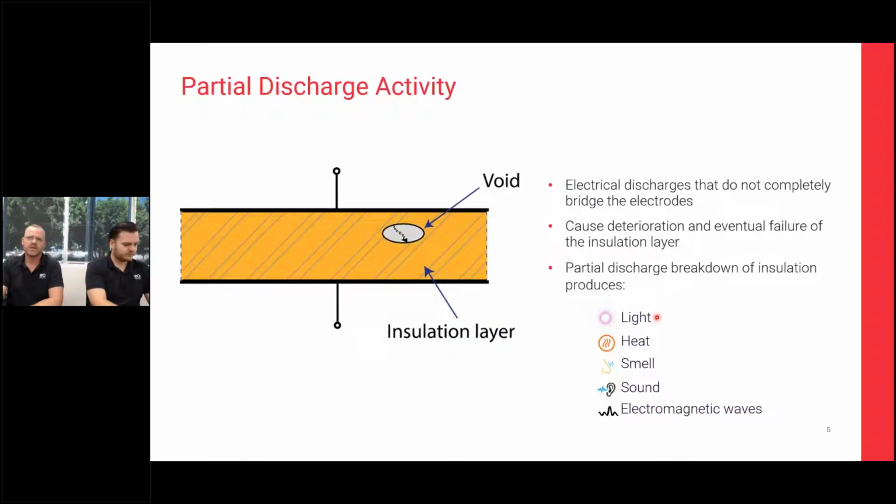Okay, so what we're going to talk a lot about today is the UltraTEV Plus 2, which is this instrument right here, which is our main handheld instrument for doing online PD testing. And what it focuses on is sound and electromagnetic waves. So let's talk about it.